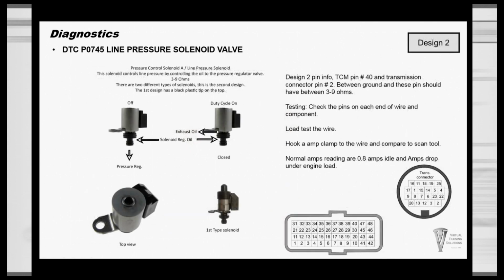Here's design 2, same thing, same resistance and all this. We are going to change the pin information though. TCM pin number 40 is going to be for design 2, and pin number 2 at the transmission case connector still. You're going to have 3 to 9 ohms to the solenoid. Either way, we can load test a wire, hook up an amp clamp. Normal amperage is 0.8 amps at an idle and drops to engine load just like the other design.